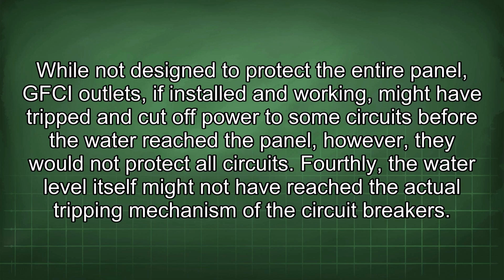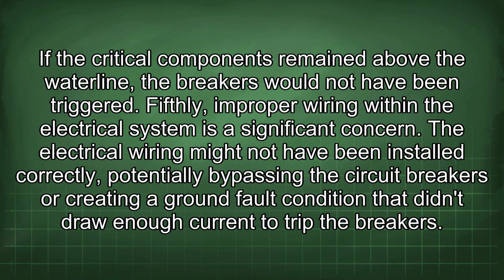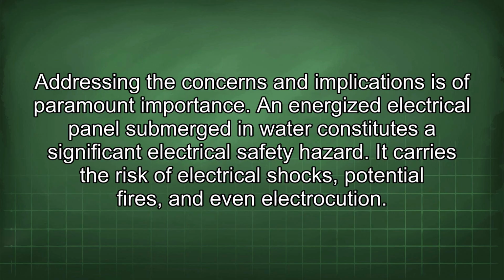Fourthly, the water level itself might not have reached the actual tripping mechanism of the circuit breakers. If the critical component remained above the water line, the breakers would not have been triggered. Fifthly, improper wiring within the electrical system is a significant concern. The electrical wiring might not have been installed correctly, potentially bypassing the circuit breakers or creating a ground fault condition that didn't draw enough current to trip the breakers. Addressing the concerns and implications is of paramount importance.